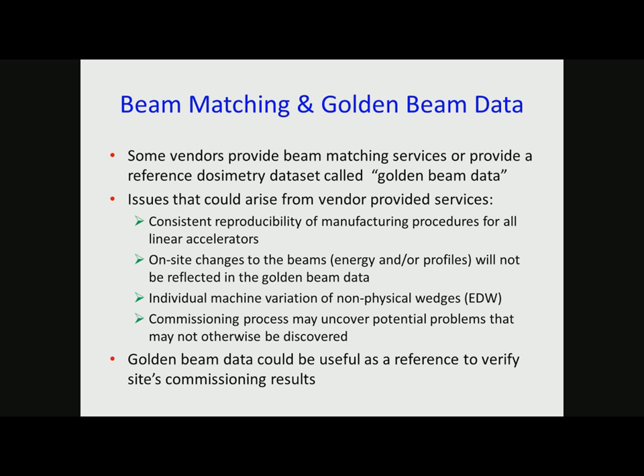They also provide you golden beam data for your treatment planning commissioning. And you put the data in the treatment planning system and it's all automated, you get the answer. However, you need to be careful because your machine may not match this golden beam data. Why? Each Linac is not a twin of the other Linac. There are slight differences in manufacturing, for example, the flattening filter.